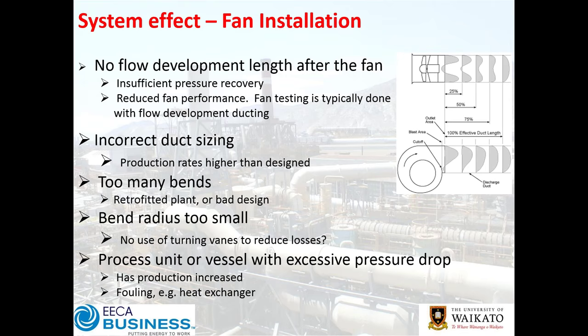The Air Movement and Control Association (AMCA) have a great document discussing the four main types of fan installation — A, B, C, and D — with respect to whether it's a free inlet and outlet, ducted inlet with free outlet, vice versa, or ducted both in and out. When you've got those ducts in and out, that can change the performance of the fan.